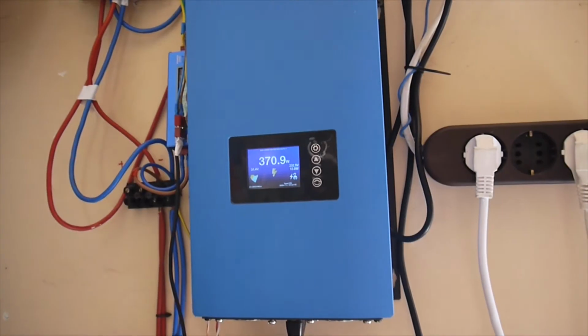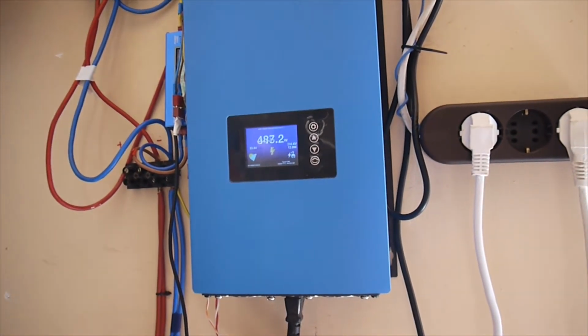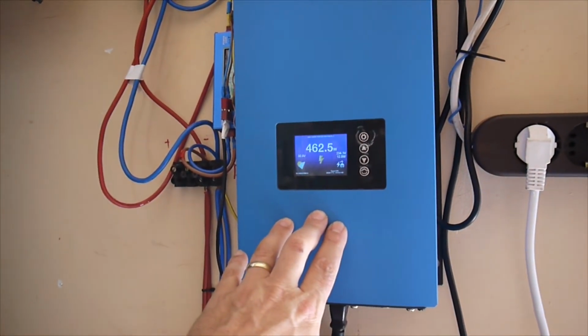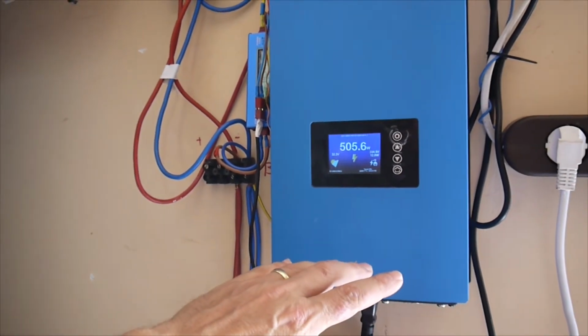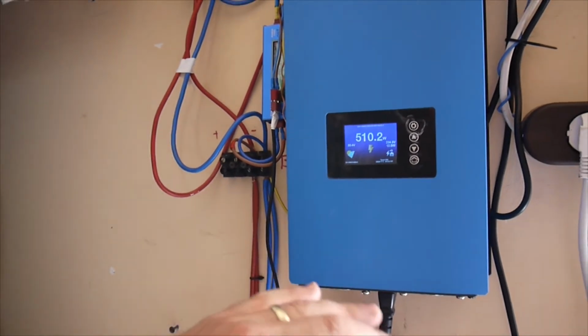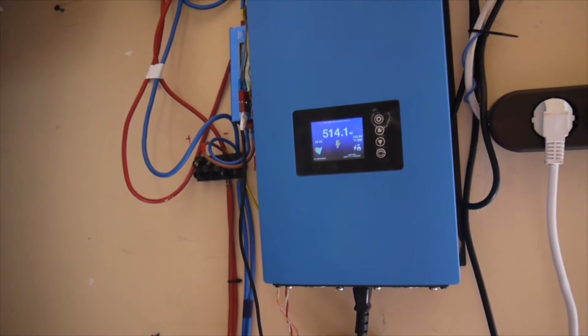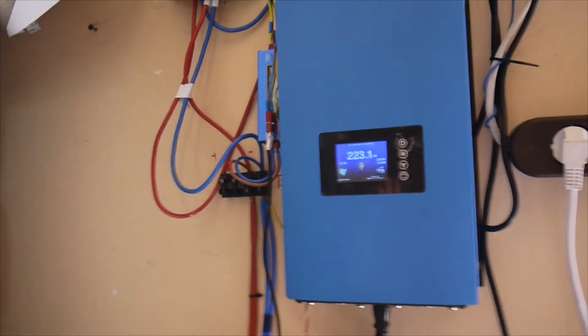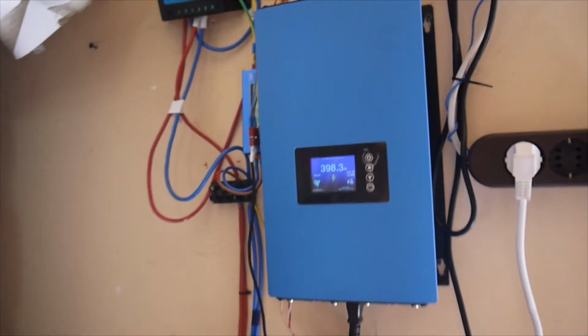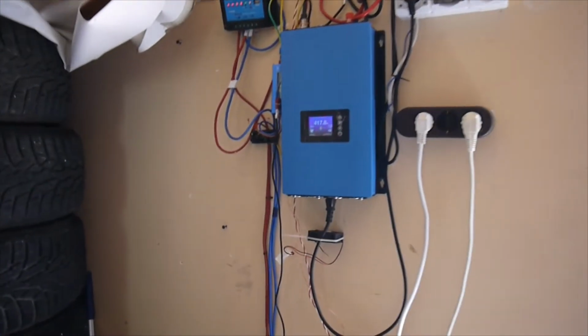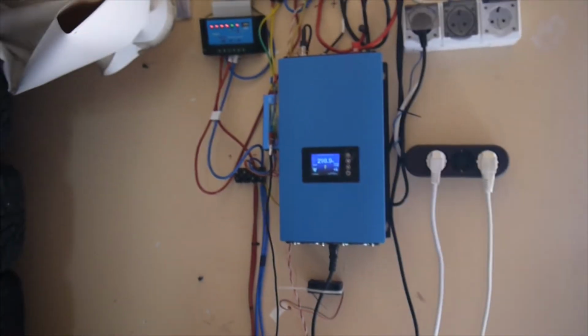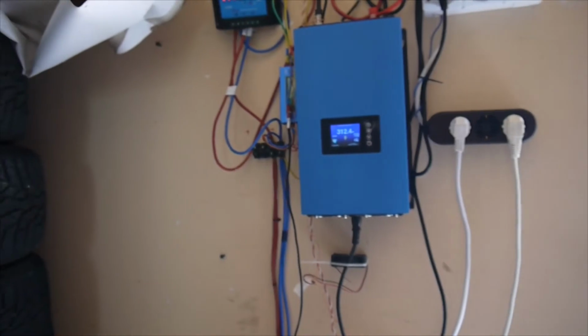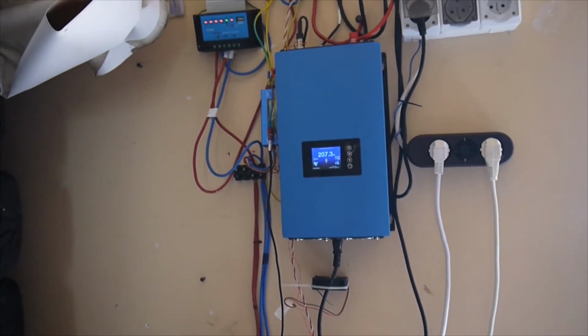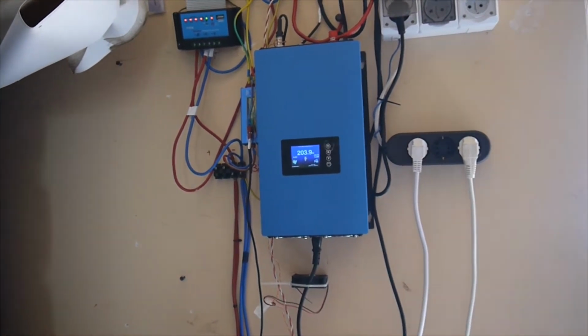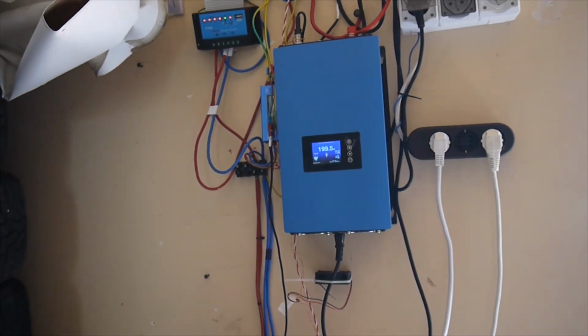So the limiter gets the information from the main phase into the house, and supplies the power from the panels to the grid in perfect concordance with the consumption. So it's not delivering more than all the electrical appliances in the house are taking at a certain moment, and that's very nice because I have no energy leaking, no power production to the grid. It's very important, because if the electricity supplier catches me with power production, it's going to be a mess. These electronic counters, so we call them counters, are so clever they can feel if you inject energy into the grid.